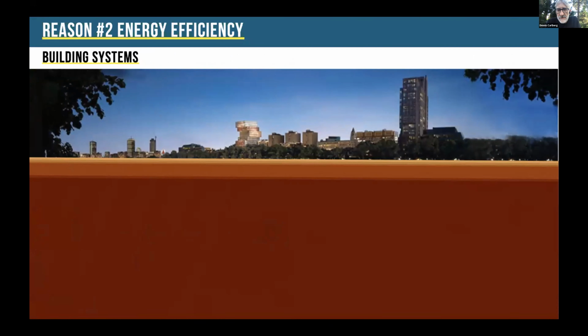Maximizing energy efficiency through building systems is a critical next step. This project employs 31 wells, 1,500 feet deep, using the Earth's thermal mass to store heat from the summer and pull that heat back out in the wintertime.